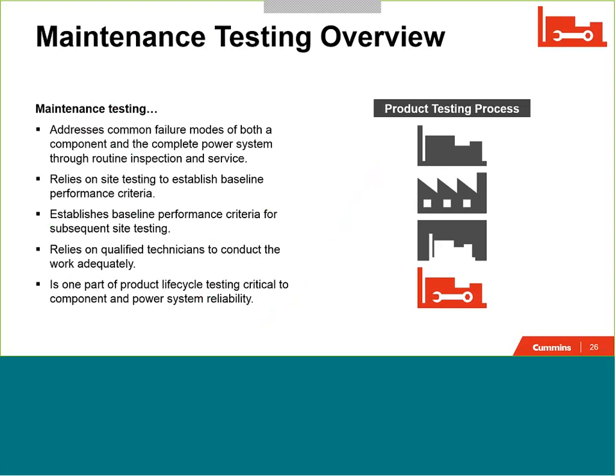And so maintenance testing is typically conducted in order to help address common failure modes of both the component and the complete power system through routine inspection and service. Maintenance testing relies on site testing to have established that baseline performance criteria. And so maintenance testing has to have something to look back at in order to understand whether or not there's a concern or there's an issue. And so that site testing, prototype testing, and factory testing all need to have been done to empower maintenance testing to do what it needs to do.